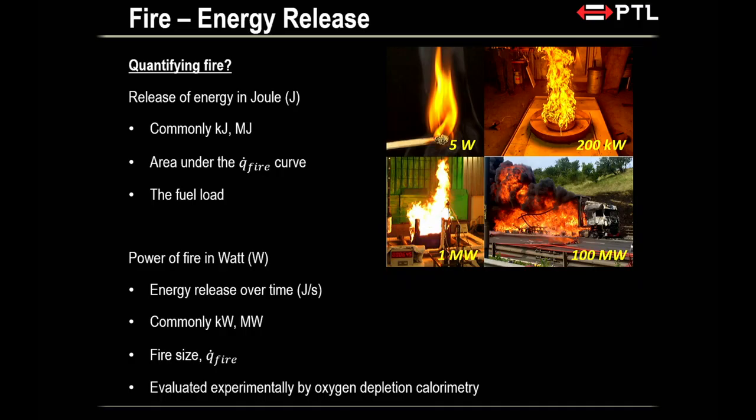Now, the video that you've seen before is actually an experiment, oxygen depletion calorimetry. So basically, we sample the smoke that comes off the fire and figure out how much oxygen has been consumed by the fire, and then you can work backwards and calculate these fire sizes. So the measurement is actually pretty accurate.